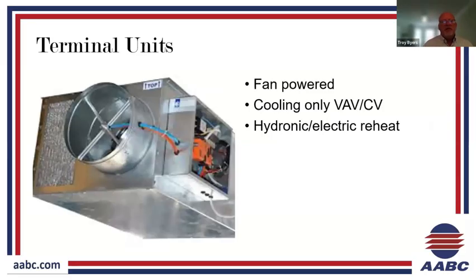Okay, and then going on into the distribution with terminal units. So this is a pressure independent fan powered terminal unit that we're looking at. And so we're going to take the medium pressure air from a VAV air handling system through that inlet and measure the airflow with those pickup tubes there that are connected to a flow ring. So an airflow measuring station there that allows this terminal unit to be pressure independent and control airflow based on the set points between a minimum and a maximum airflow.